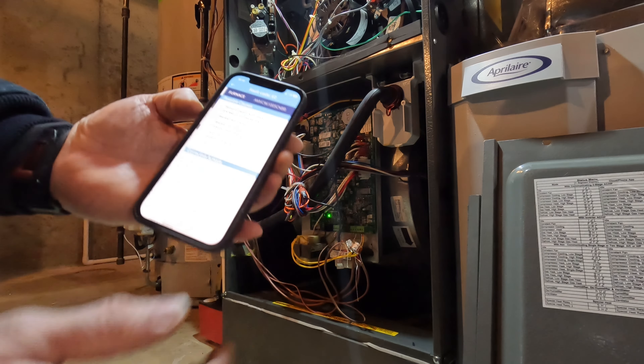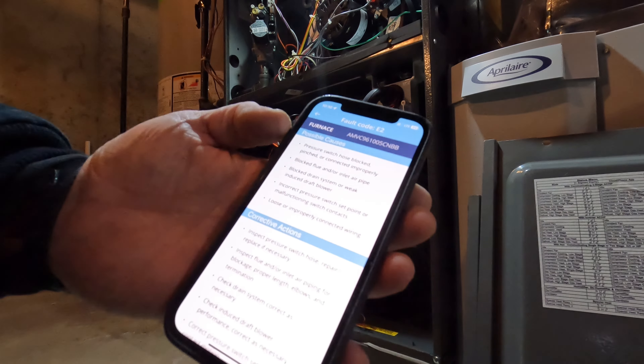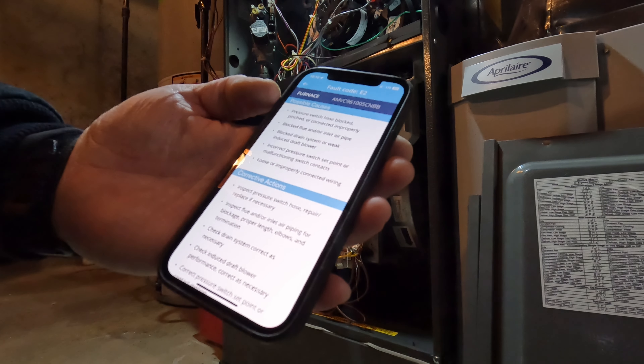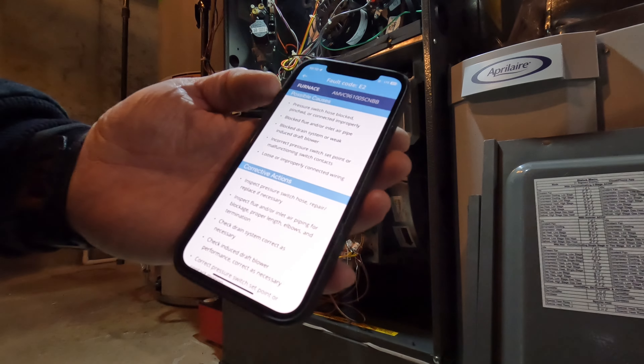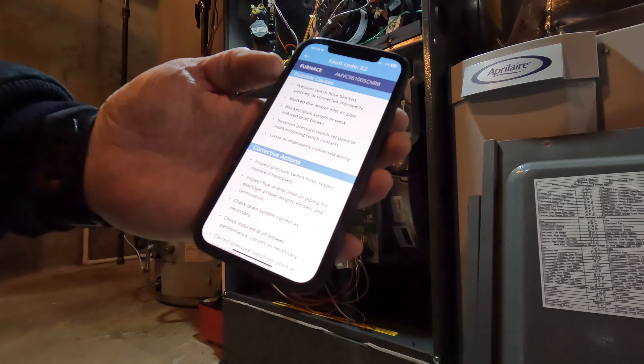It gives you the fault effects. So I'm assuming there's water in this. Pressure switch hose: blocked or pinched, connected improperly, blocked flue or inlet pipe, blocked drain system, weak induced draft blower, incorrect pressure switch point, or loose or improperly connected wiring.